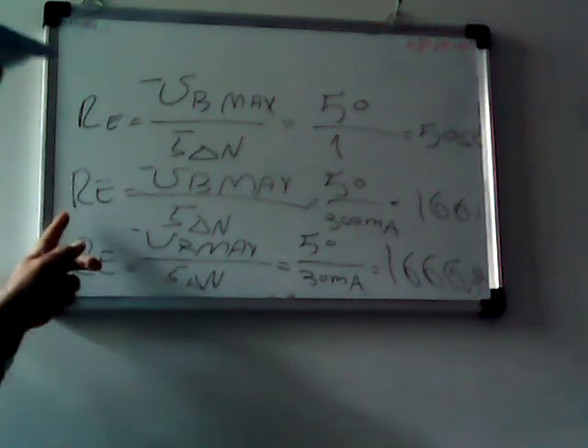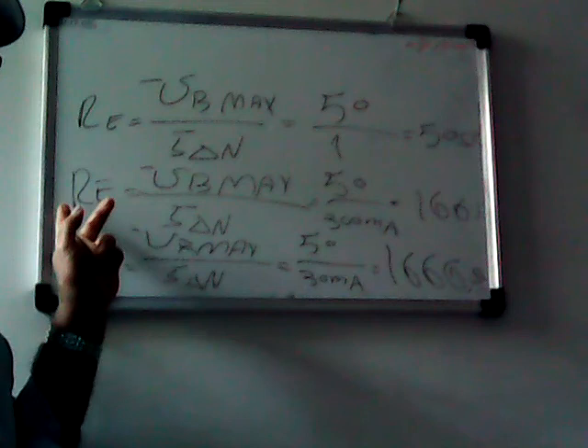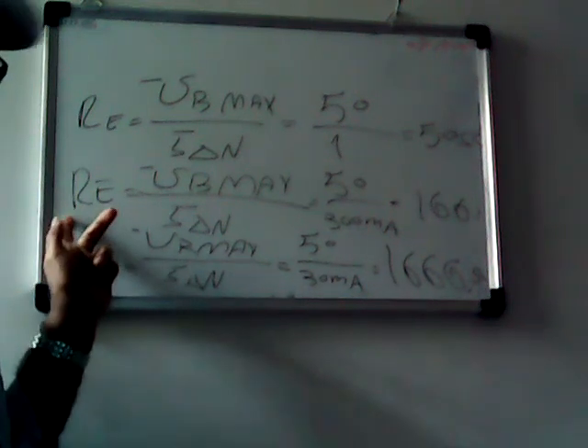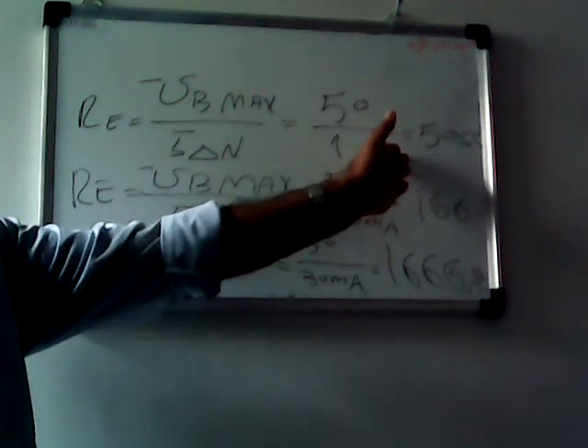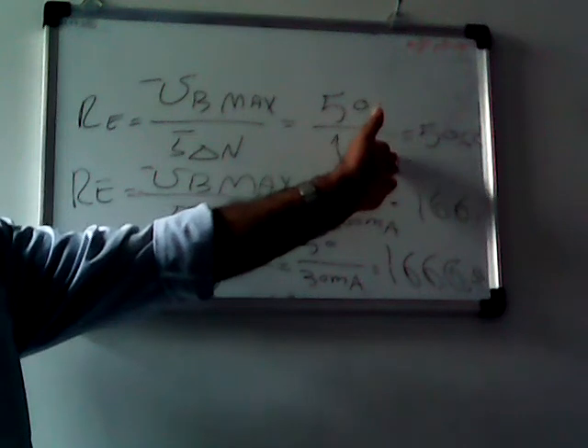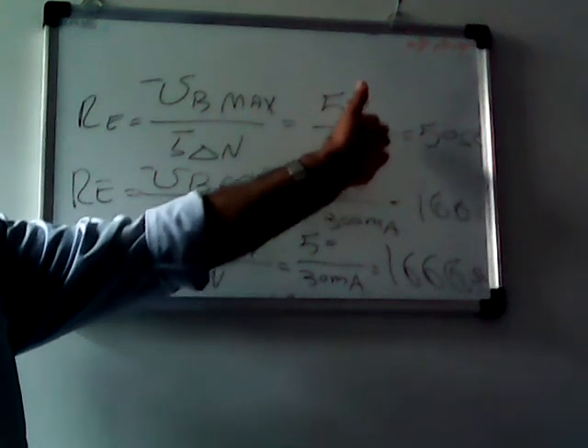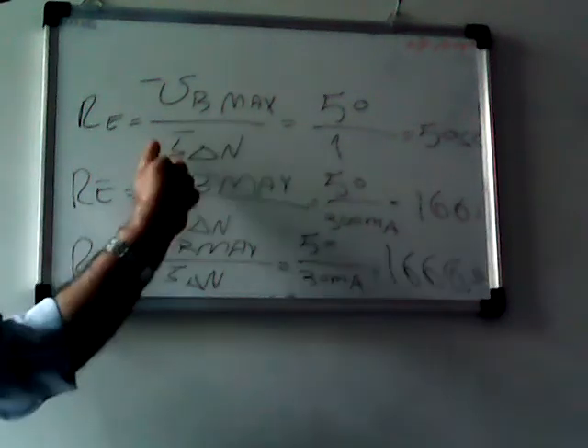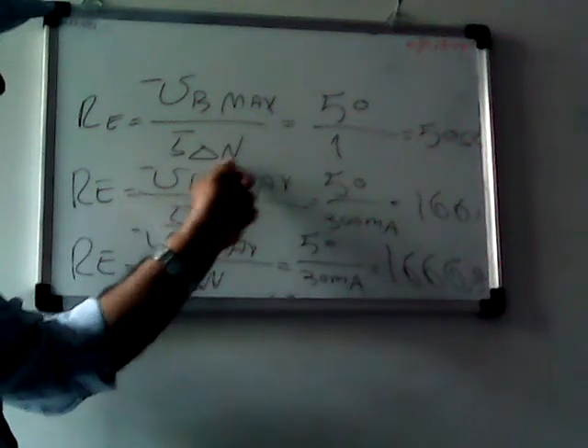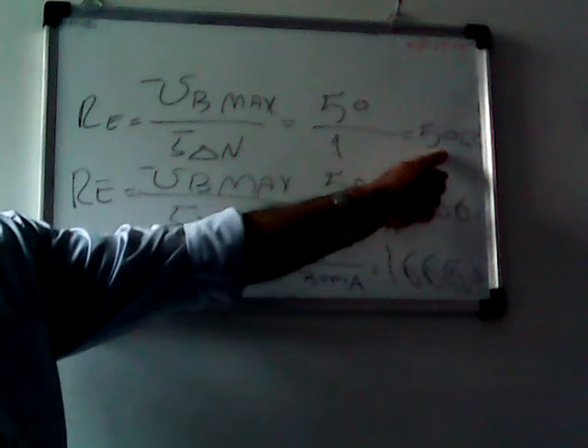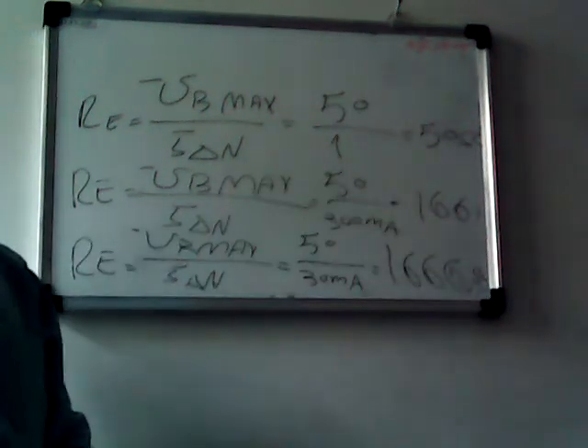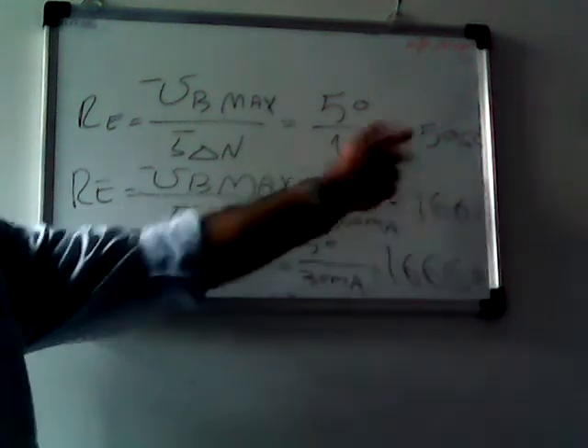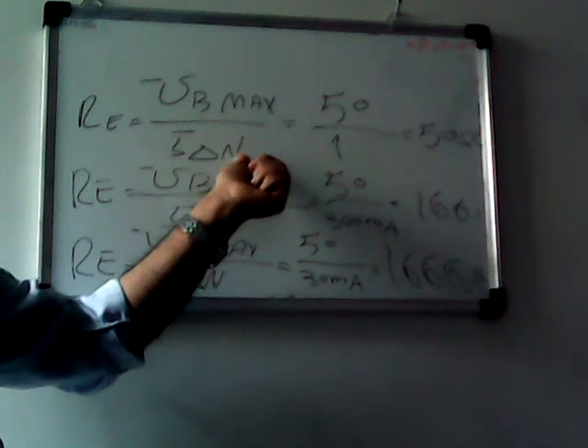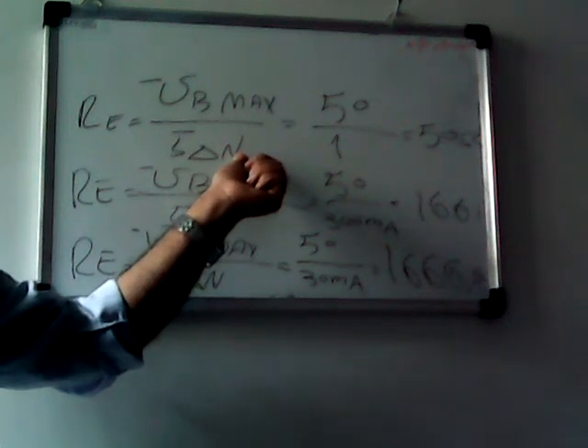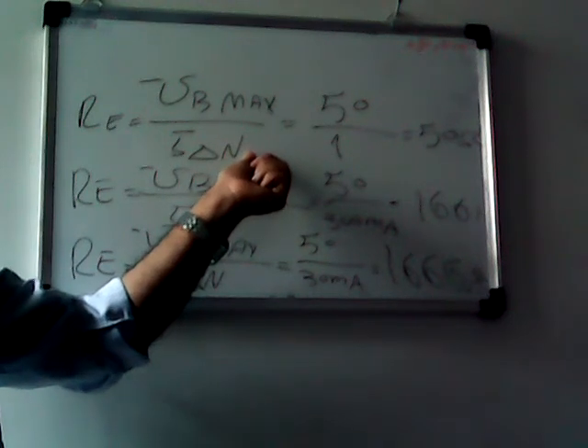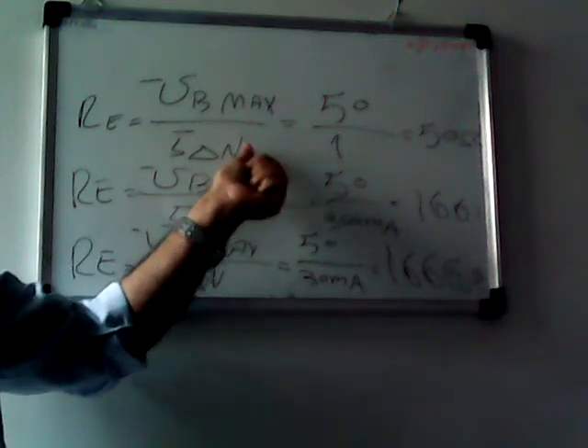The advantage is that when you use ELCB in your installation, you don't need 2 ohms in RE — the electric earth pit, earth rod, earth electrode of 2 to 5 ohm. With ELCB and a rated I delta N, if you just have a pipe as an electrode dug into the ground, 50 ohms is enough, because the ELCB acts when a person touches the live wire, the phase wire.